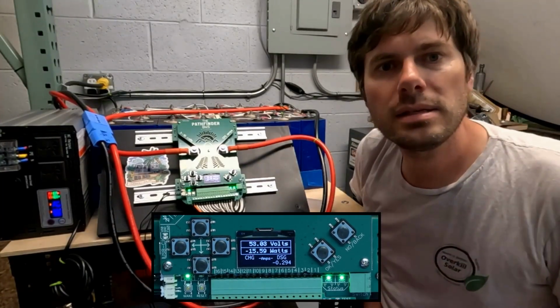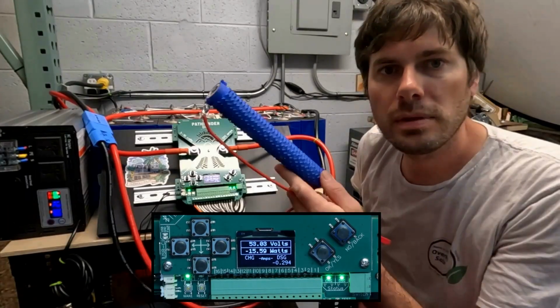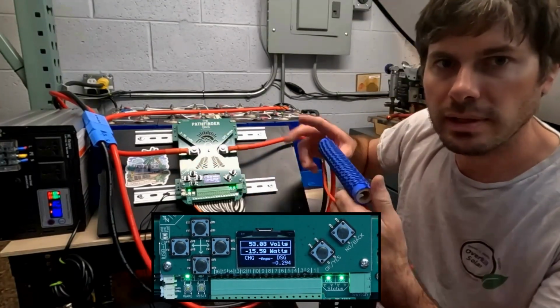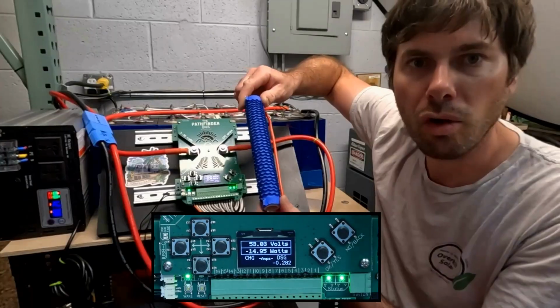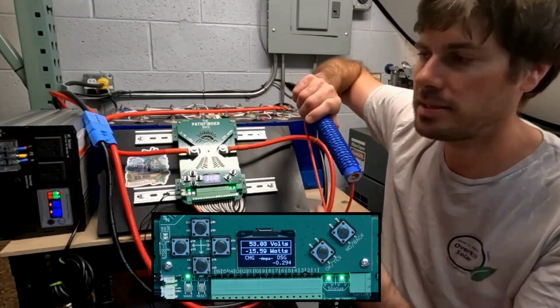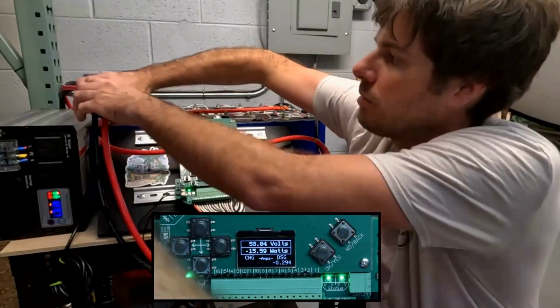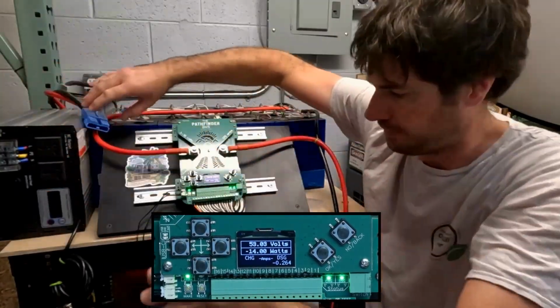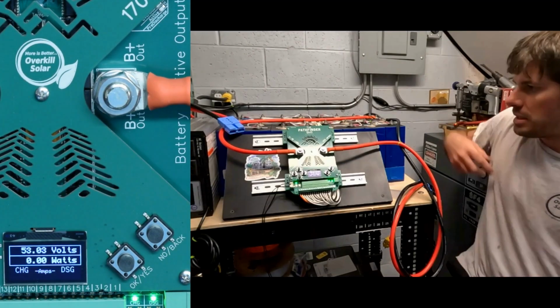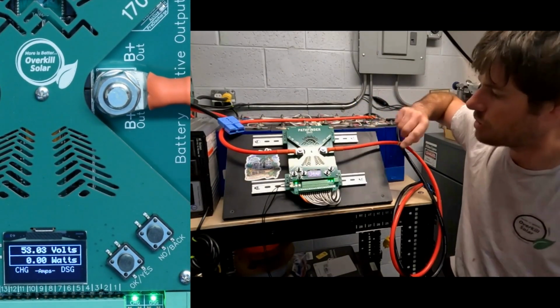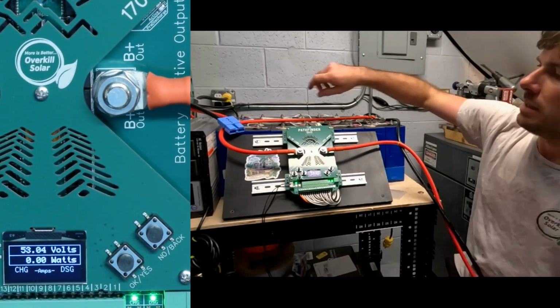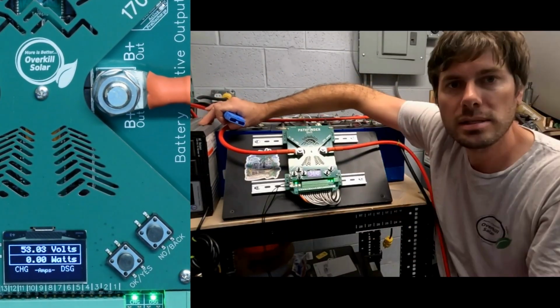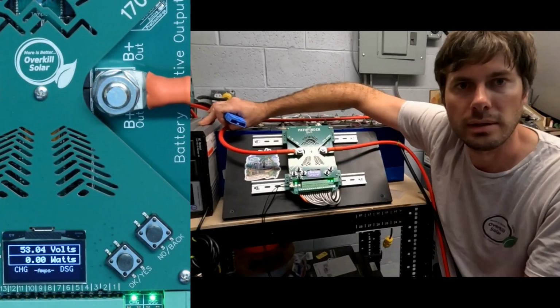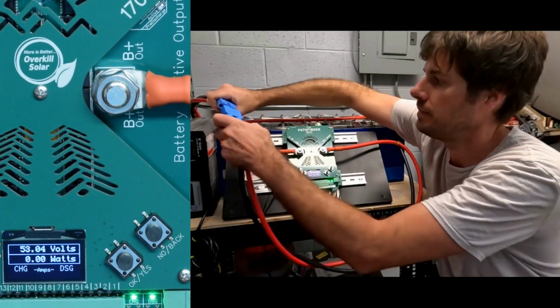So now let's demonstrate what can happen if you have a large load on the system. This is a 0.7 ohm load resistor. I'm going to connect this to my system, and then we're going to try the pre-discharge circuit. Alright, now that we can see the pre-discharge indicators and the charge-discharge indicators, let's try this. When I plug in the inverter, the capacitor inrush current is going to trigger the short circuit detection.